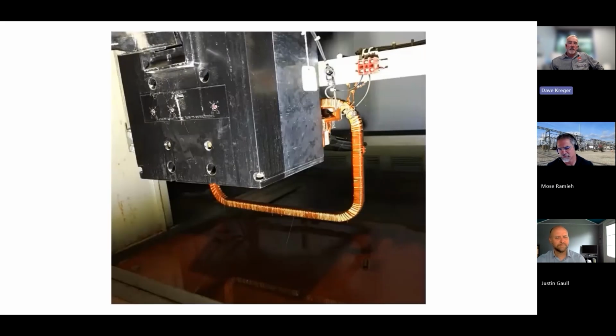What sticks out to me on this photo is obviously the lack of insulation around that zero sequence CT. And yes, it is sitting on a bus bar in the back. The only thing that's protecting that right now is a bit of lacquer around the windings of that CT. But if you look at the CT wires, the leads going up to that terminal block, it looks like those wires are melted together. I can't tell from the photo, but that's a common issue.